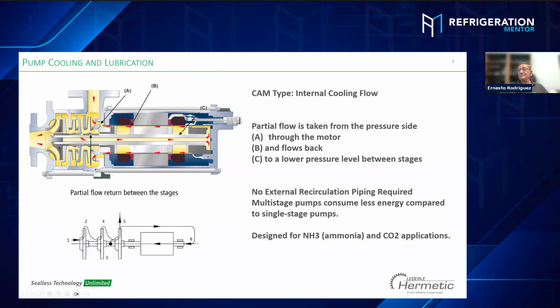We can see how the multi-impeller pump runs. Okay, why do we have two different designs? I want to explain in the next slide what exactly. The fluids run opposite because we have a high pressure on the discharge, and we will try to get the differential pressure. We have calculated approximately the 10 psi differential pressure from the discharge and the internal part of the pump. Right here is the approximately 10 psi. We have this diagram to show P1 is number 5 and P2 is number 3. Basically, P1 is higher.